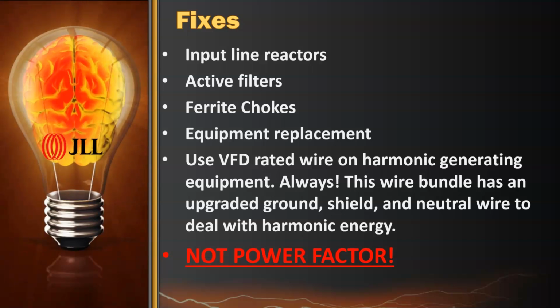They're pretty inexpensive. An input line reactor for something like a 1,000-ton chiller is, by comparison, probably $15,000, something like that. An active filter is significantly more expensive. It might be 3 times that. It might be 50 grand. So I like ferrite chokes for that reason. They're used in cell phone towers all over the place. Ferrite chokes are used everywhere to deal with harmonics, and it's low tech.